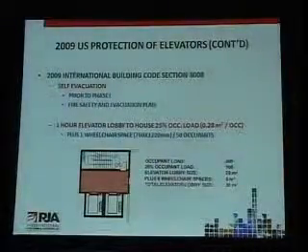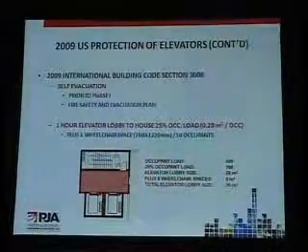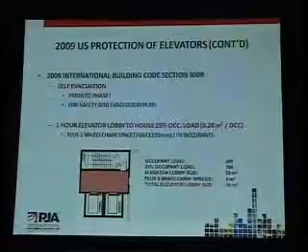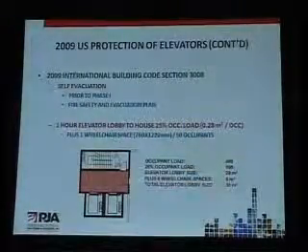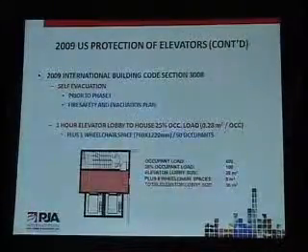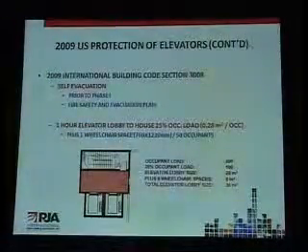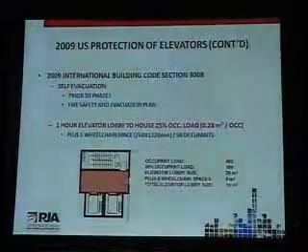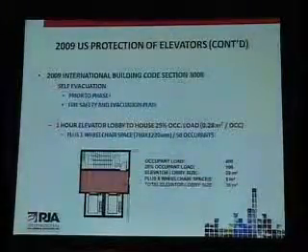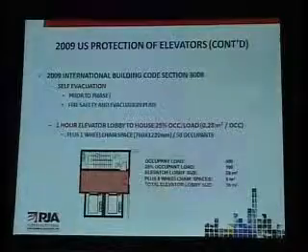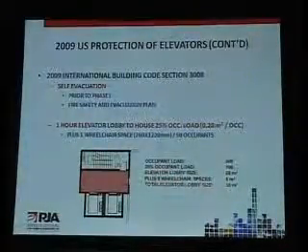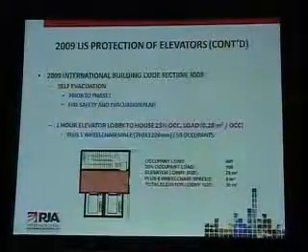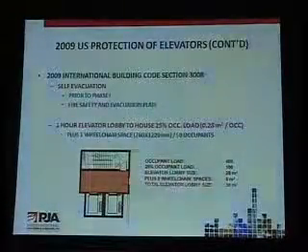So, for example, let's say you have a decent-sized floor plan with a restaurant in it, and you have a couple of 1,500 millimeter stairs. You're getting occupant loads up around 400 occupants. Well, you need to accommodate at least 100 occupants within this vestibule. And so when you start adding up the numbers and figuring out how much space you need, plus you need to add a wheelchair space, now you're looking at a vestibule of about 36 square meters, which, if you're planning a core and you're already into detailed design in your project, may cause you to actually have to redesign your entire core.